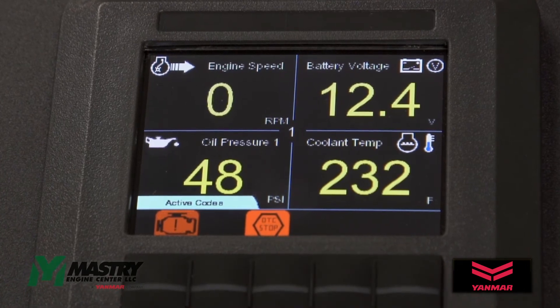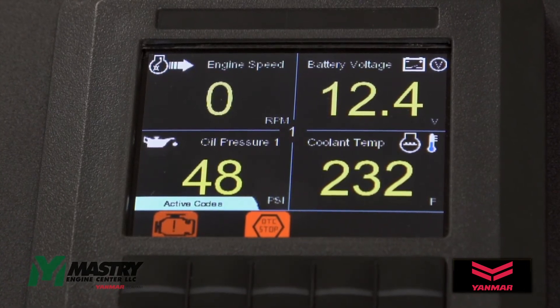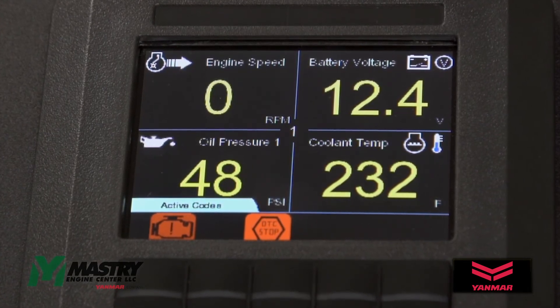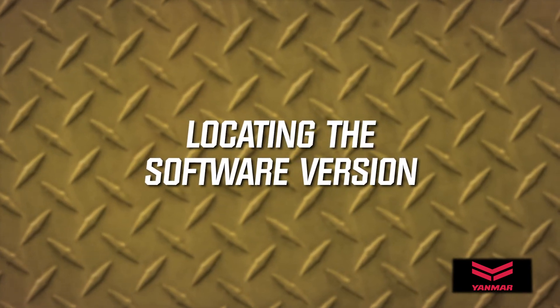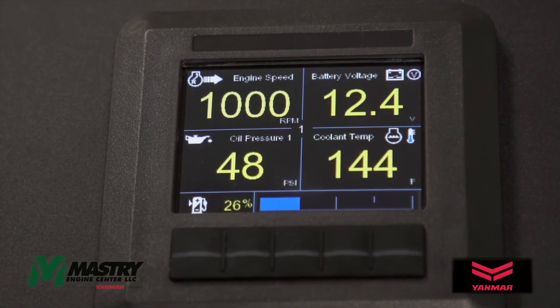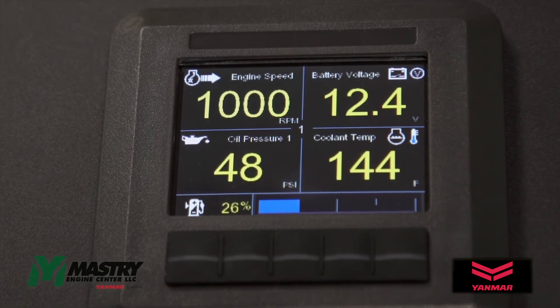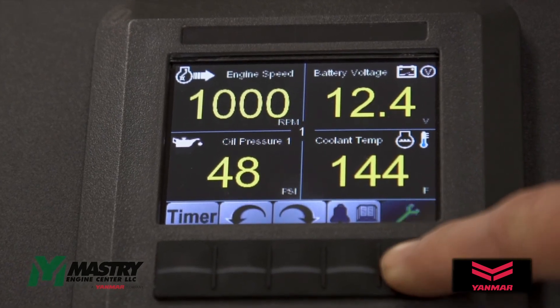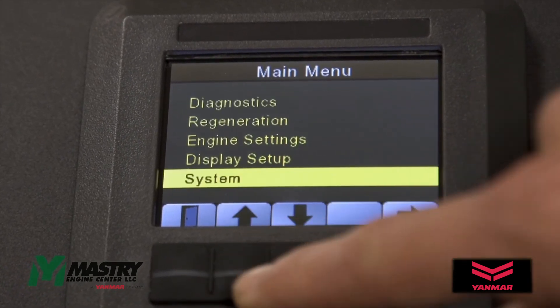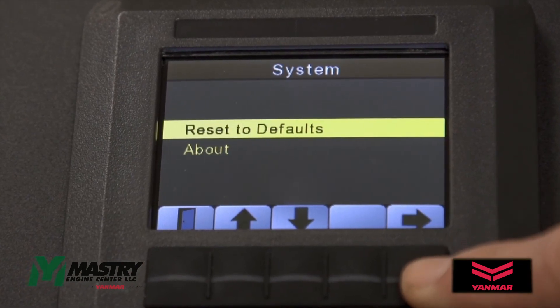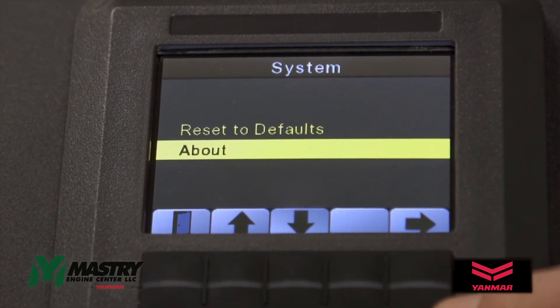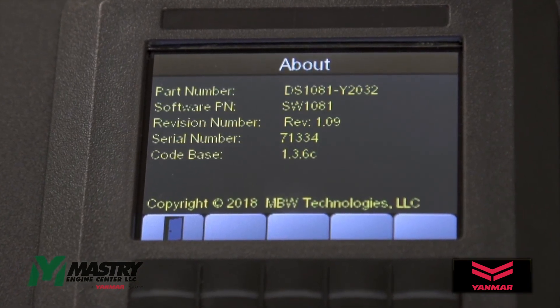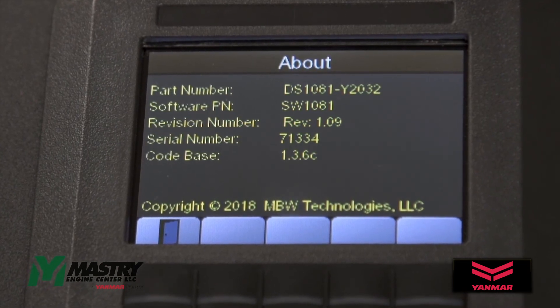The two fault codes that can shut down the engine are coolant temperature fault codes and a low oil pressure fault code. For diagnostic purposes, it may be useful to know what software version is installed on the panel that you have. To get this information, enter the setting menu, arrow up to get down to system, and then hit enter, and then arrow down to the about section, and hit enter. This will be the information that you will need to provide to troubleshoot what a potential software issue may be.